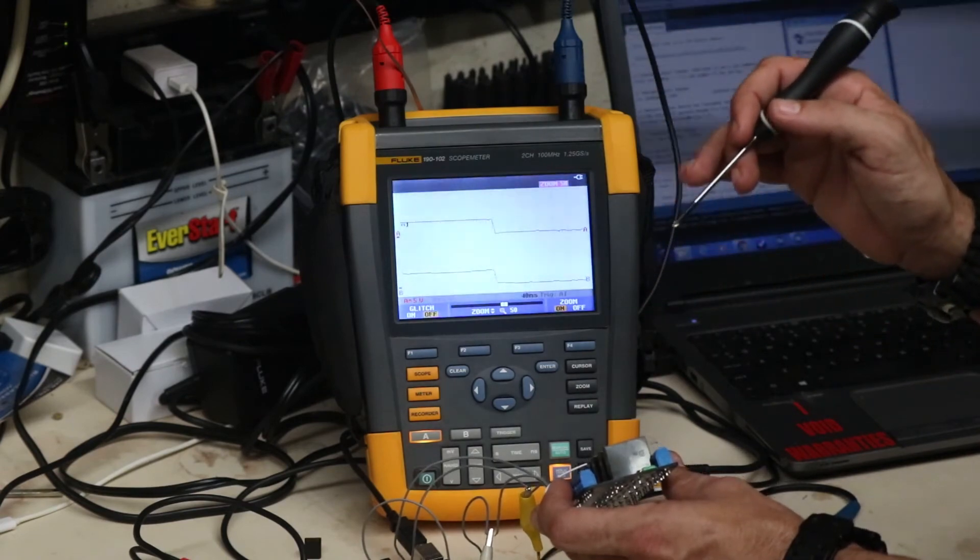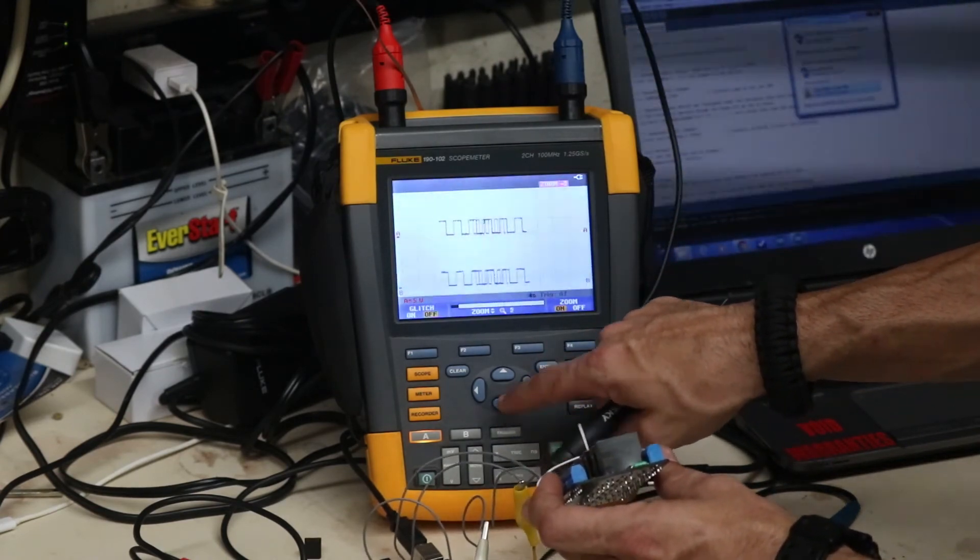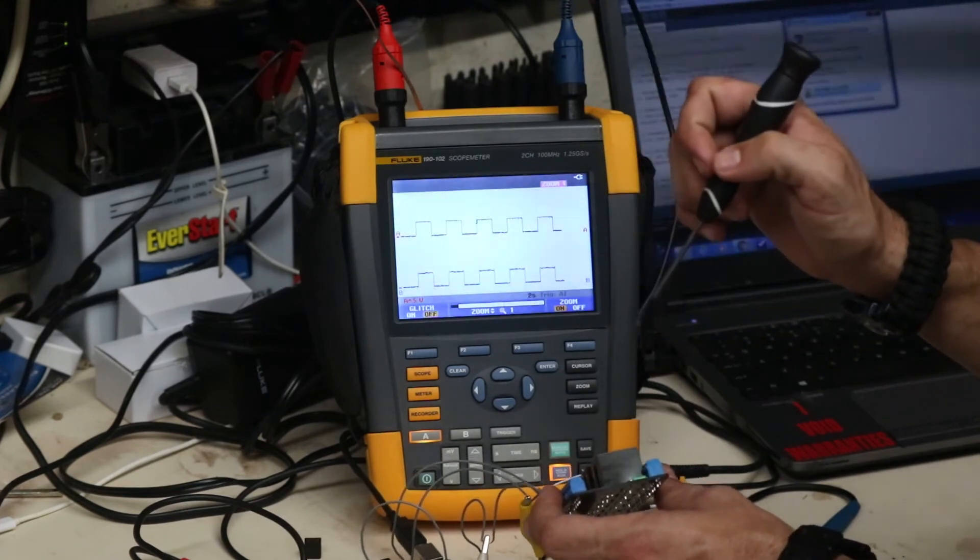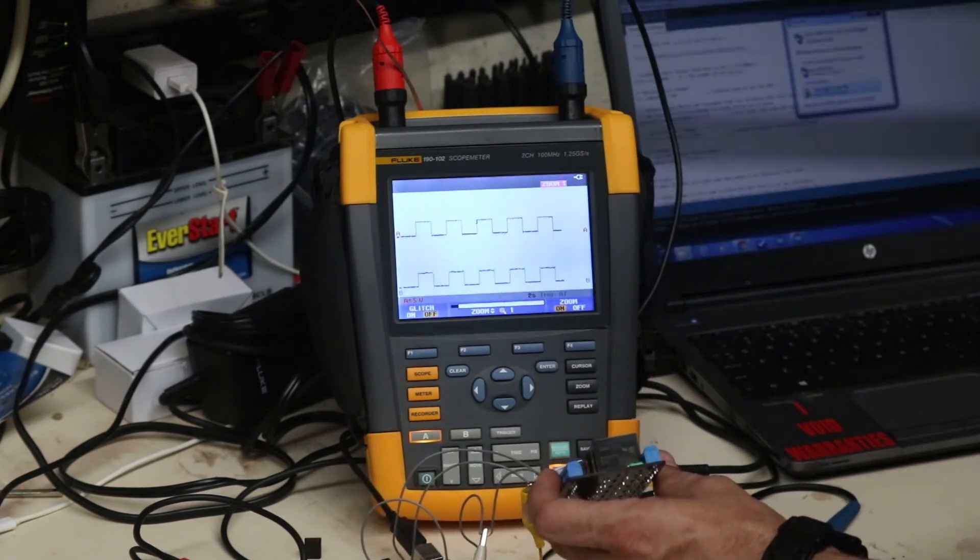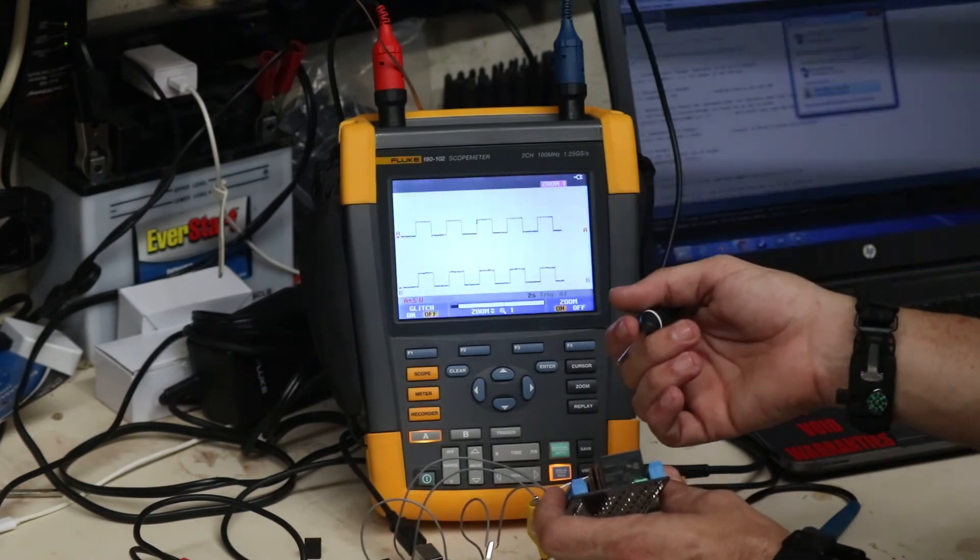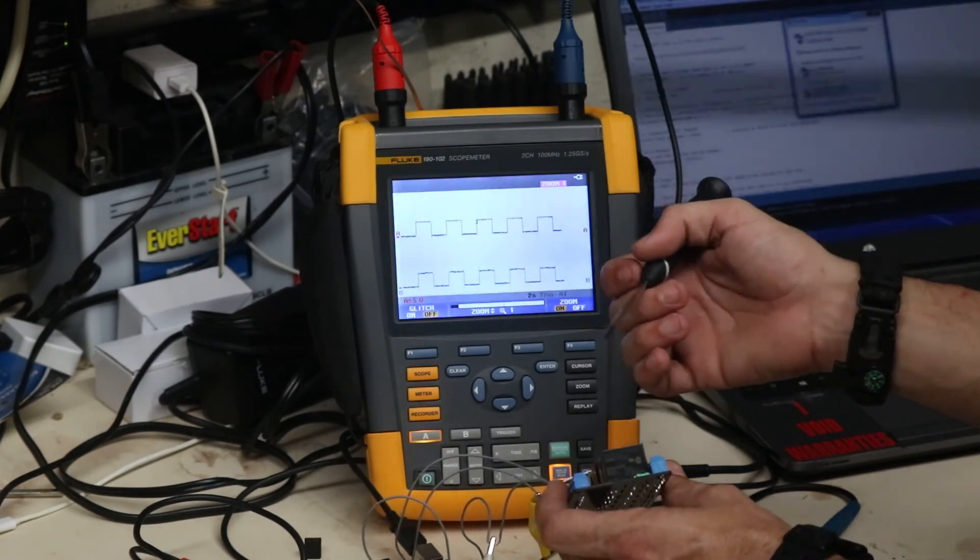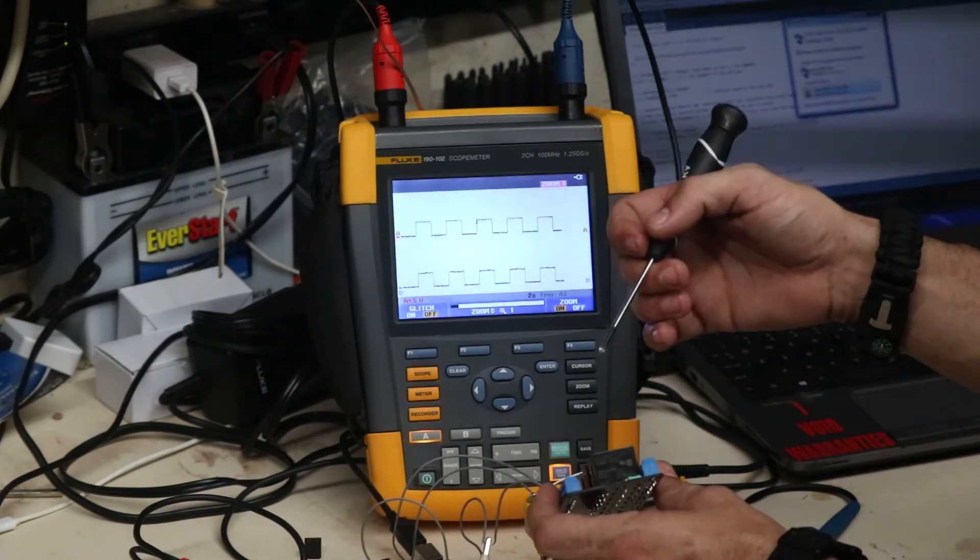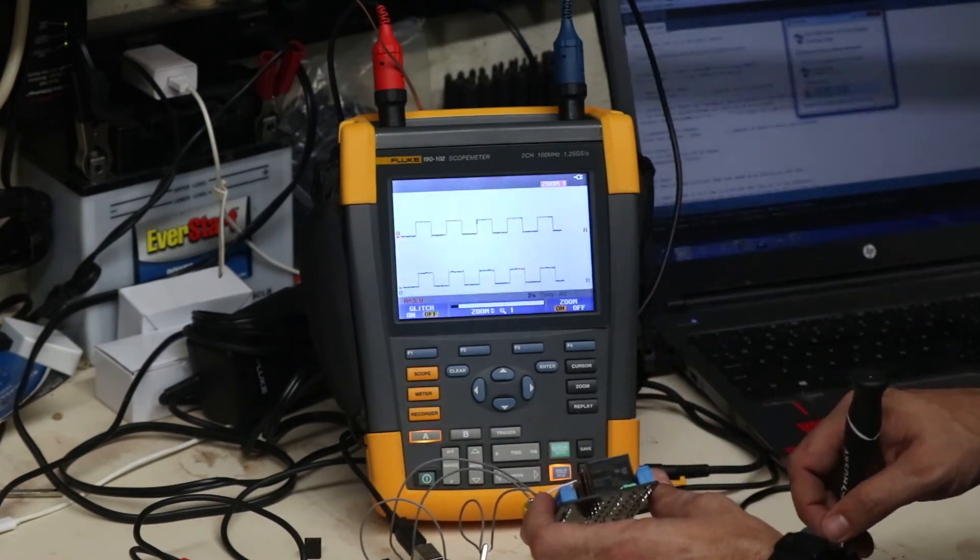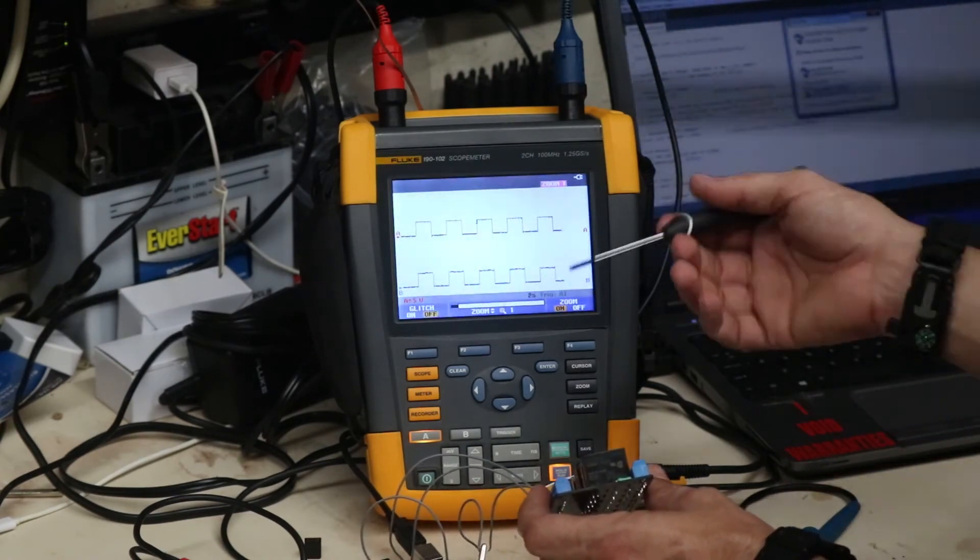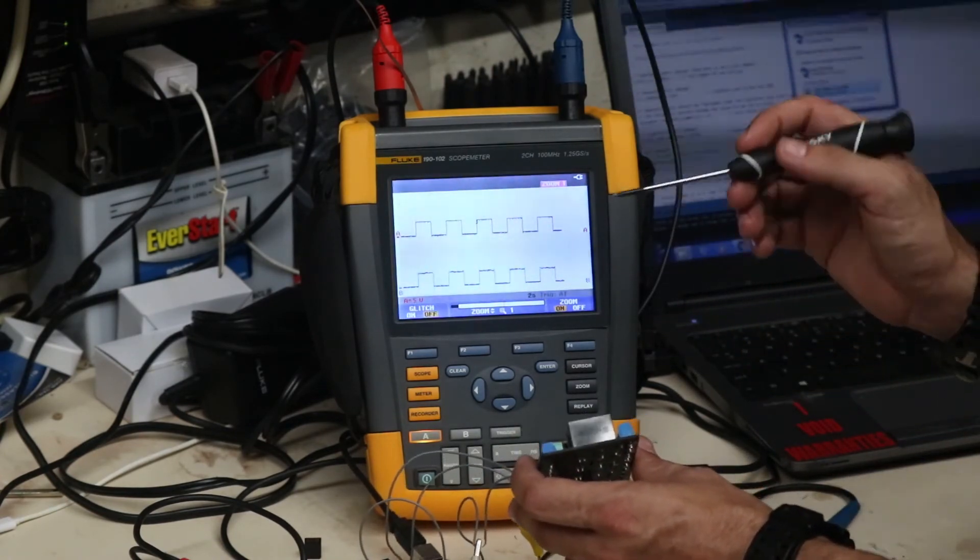I couldn't find anything on the solid state relays in the way of any type of life expectancy, and that's probably because the internals of it are very similar to a transistor. So they're all silicon based, there's no moving parts, there's really no contacts to arc against or wear out, there's no copper pads in there or copper contacts like they are in the mechanical relays, and there's no coil moving back and forth. So there's no moving parts.